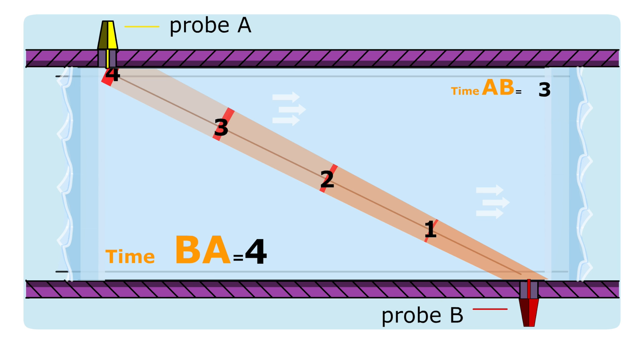Then, the device sends another ultrasound this time from the red probe and measures the time needed for the ultrasound to reach the yellow probe. Therefore, the two travel times are different. The travel time against the stream is longer than the travel time with the stream.